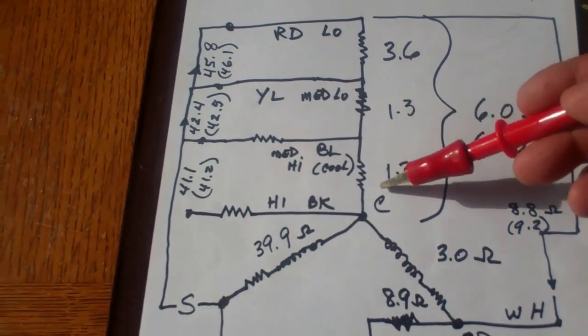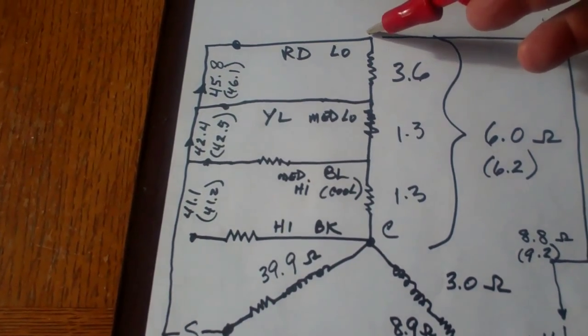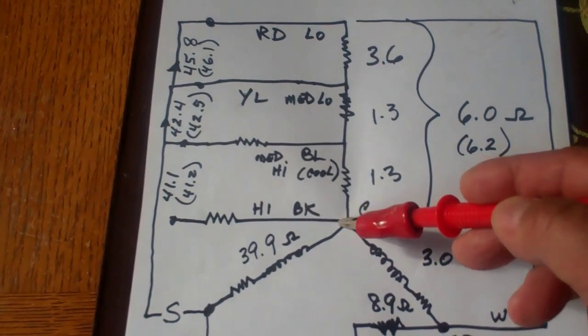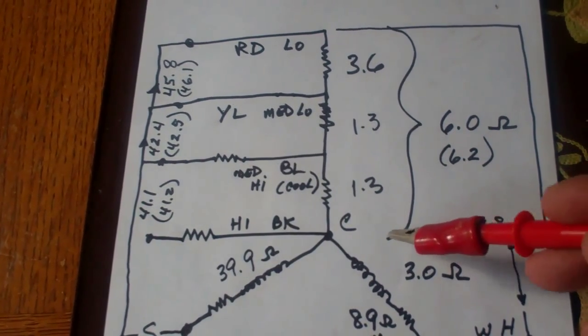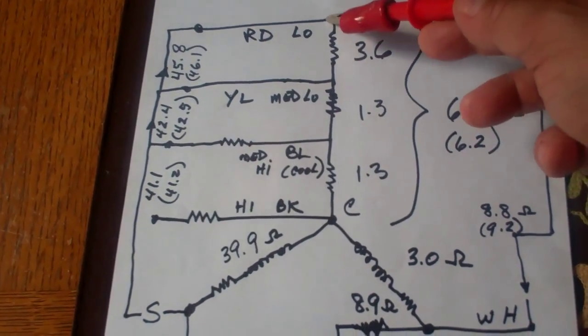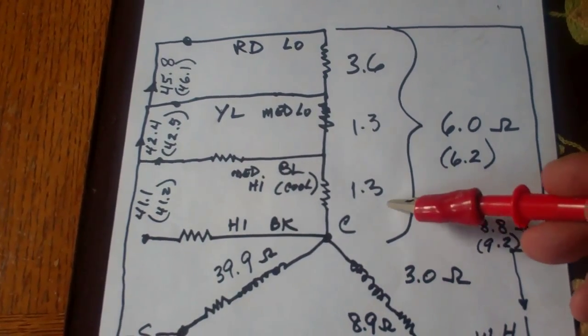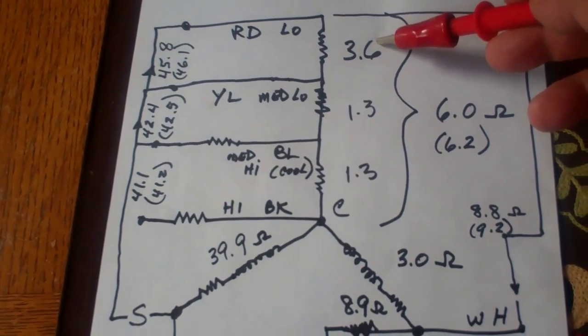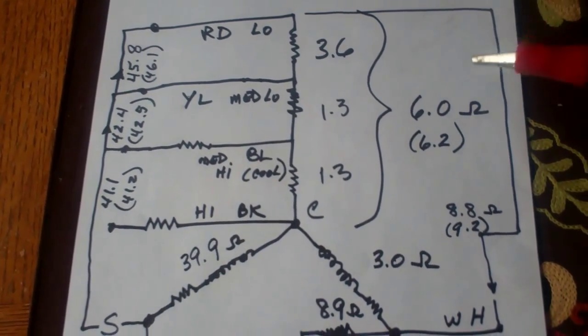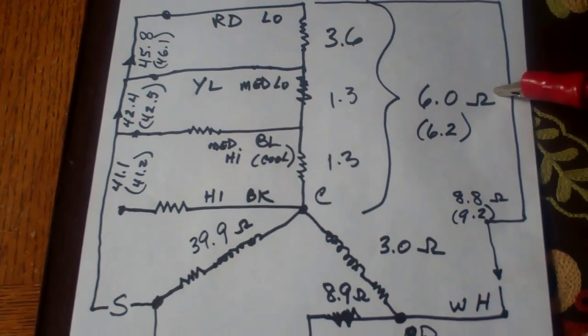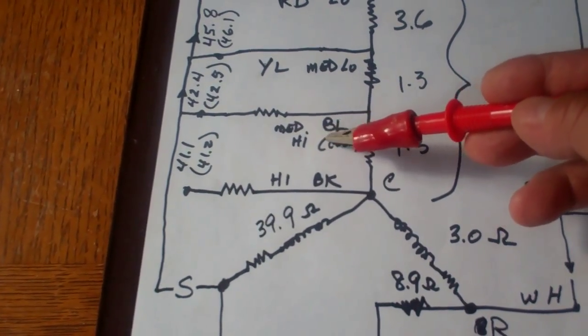Now that you've ohmed out the resistance for each individual segment, you can see that it makes sense now. If you take a measurement for instance from red to black, you should get the sum of each of these segments. So in this case, from red to black, we would be looking for 6.2, that would be the sum of these three. And what I actually got was 6.0, which is close enough. That's right in the ballpark. That's what we're looking for.